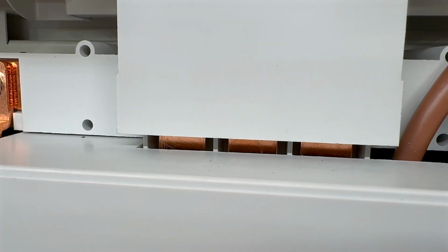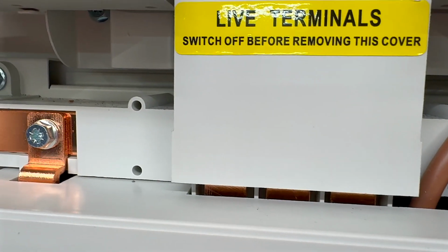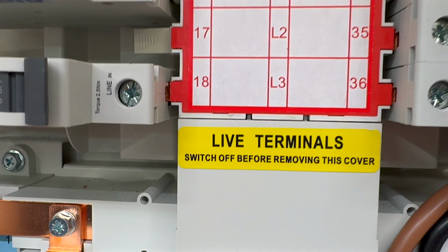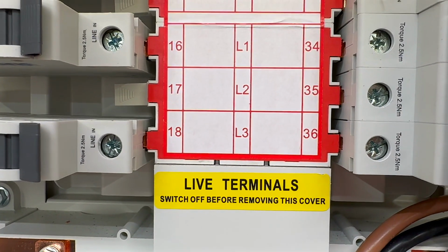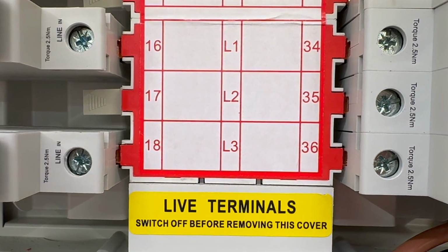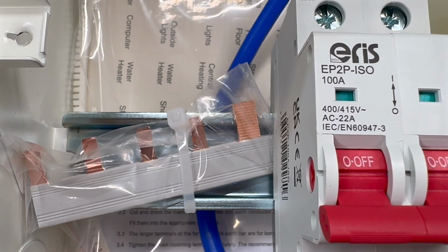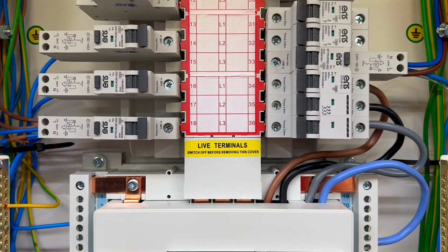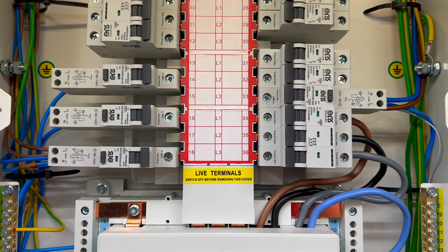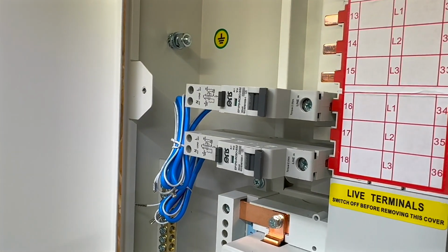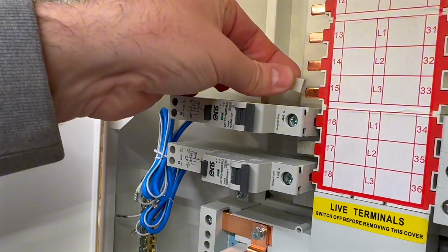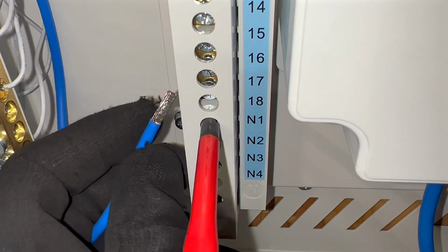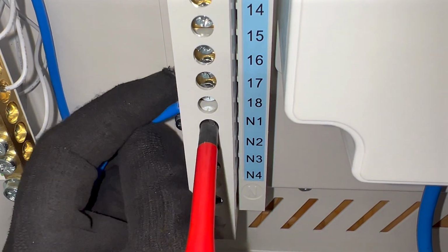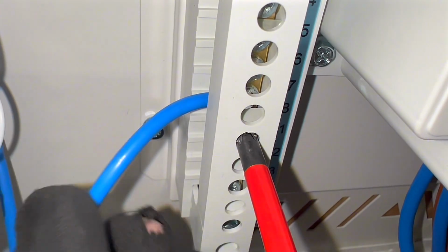Once the supply passes through the main switch, the line conductors are distributed to the outgoing circuits via internal copper bus bars arranged in an L1, L2, L3 configuration. Unlike residential consumer units, 3-phase boards come with pre-connected bus bar wiring. This means you only need to attach the incoming and outgoing devices to the exposed bus bar tabs, simplifying the installation process. The neutral connection is routed from the incoming switch to a neutral bar, typically made of brass, positioned on either side of the board.